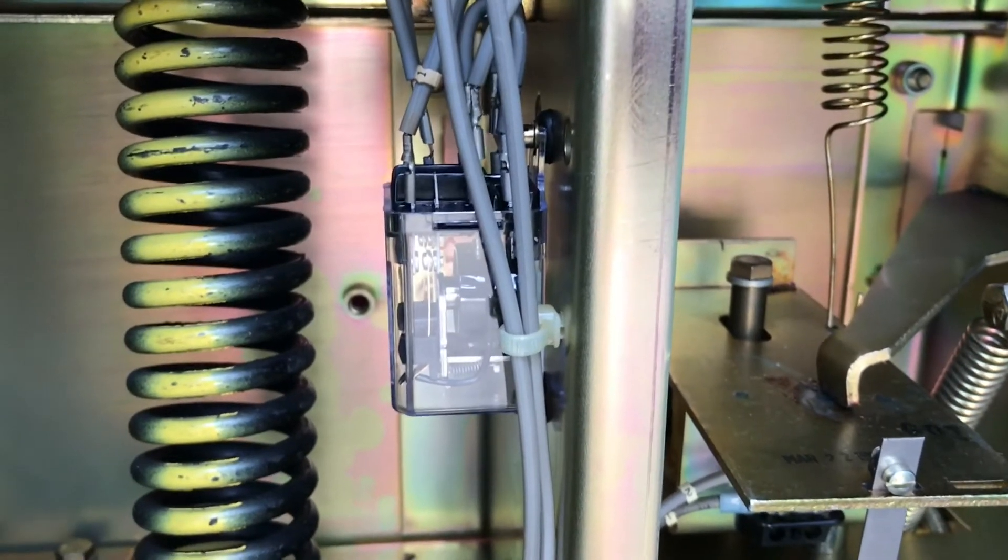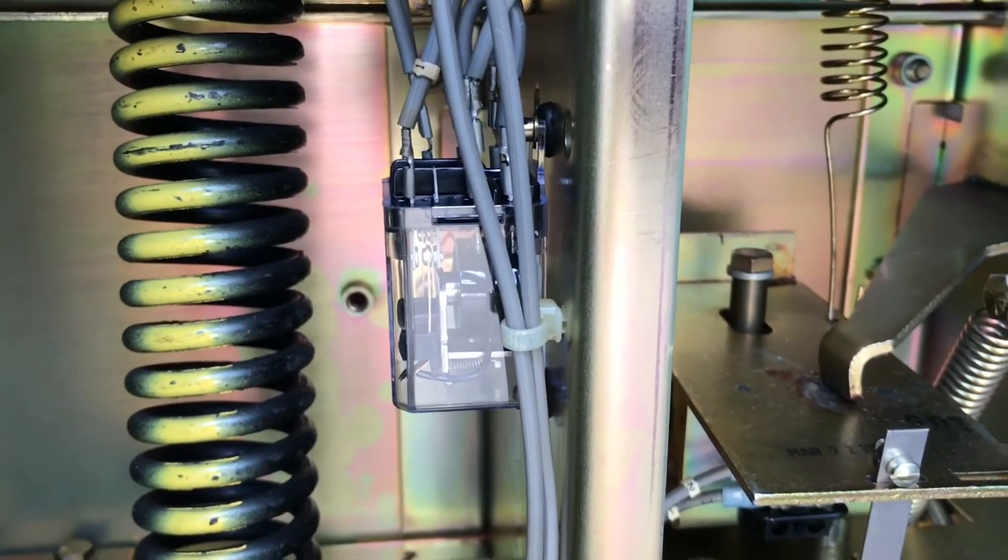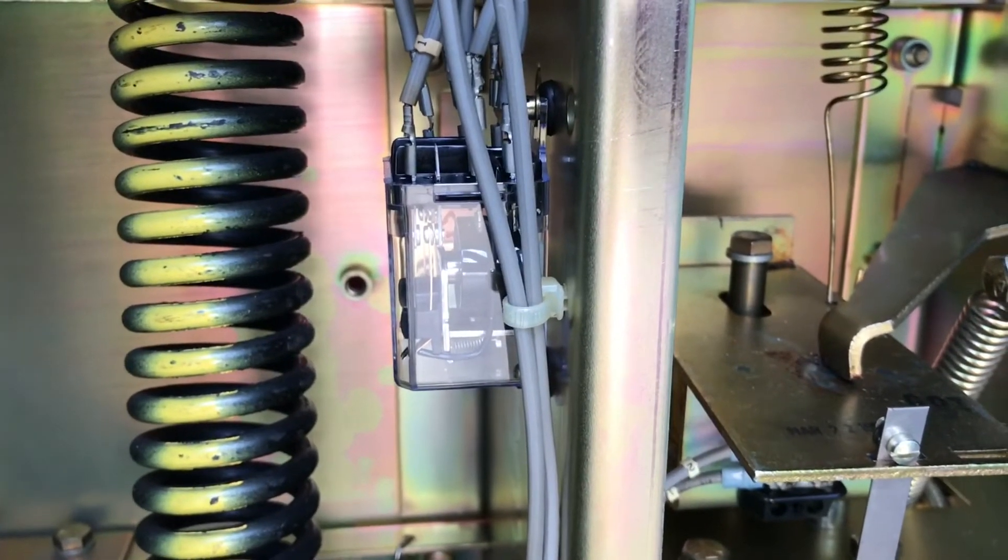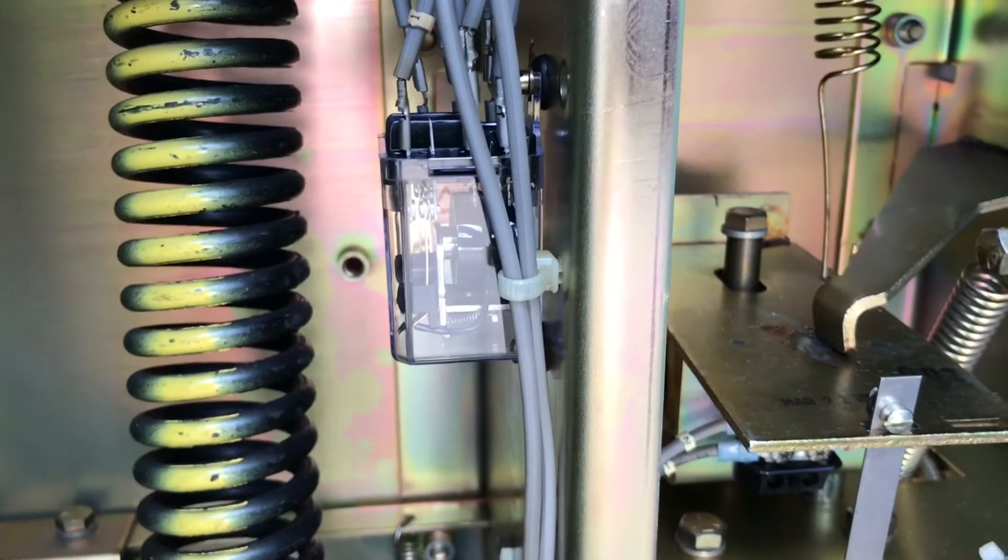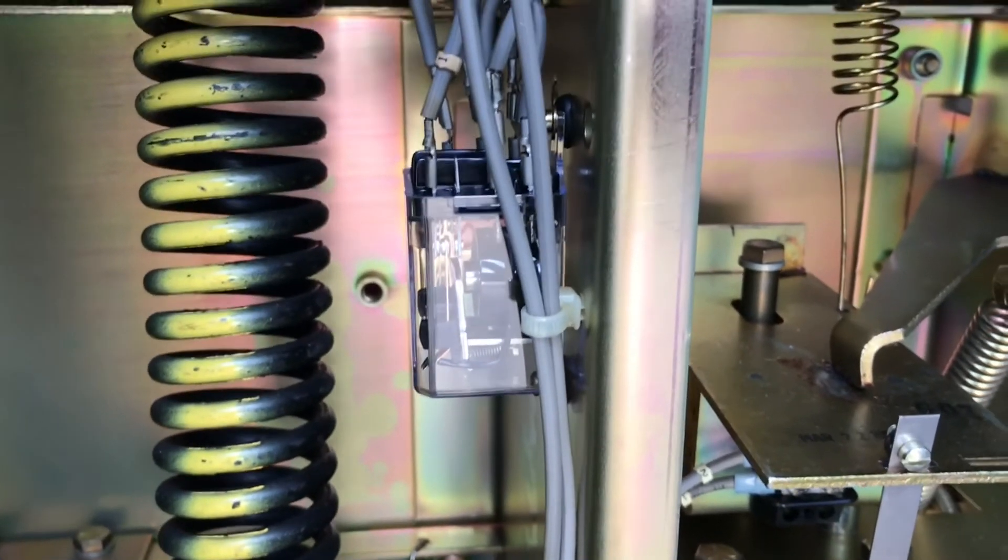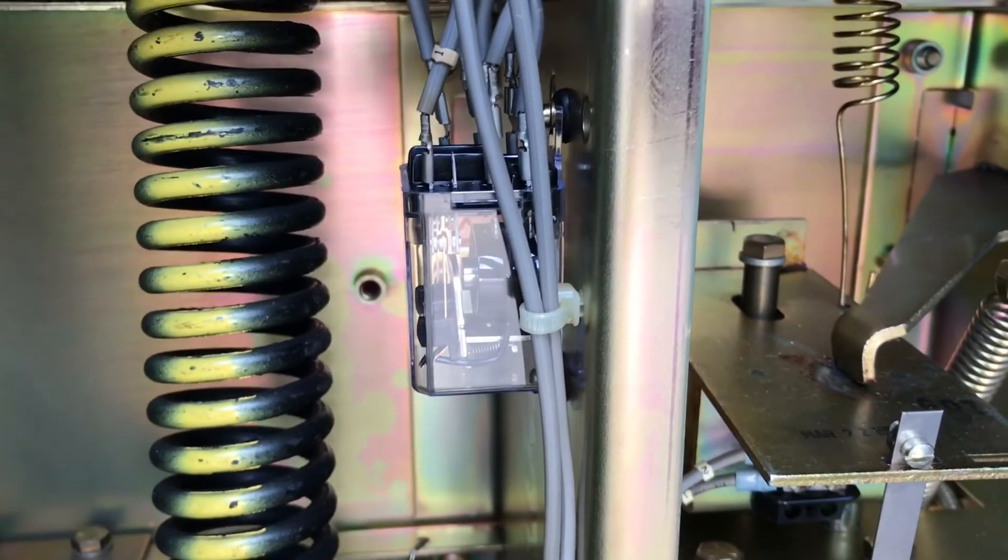I'm still holding the switch, that anti-pump is still energized. But with that being energized, it opens the circuit to the closing coil so that it can't attempt to close again. All right, I'm going to release the control switch, and the anti-pump relay opens.